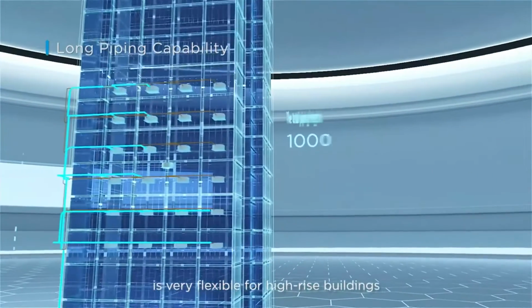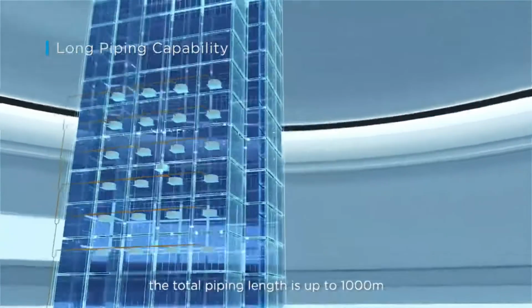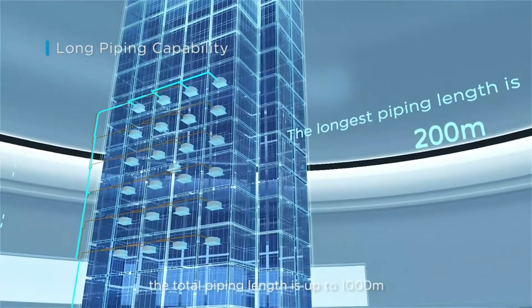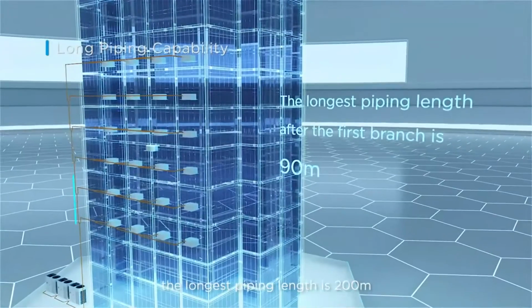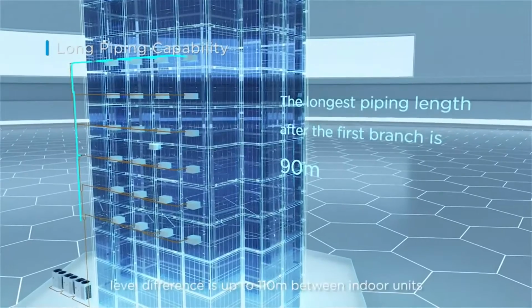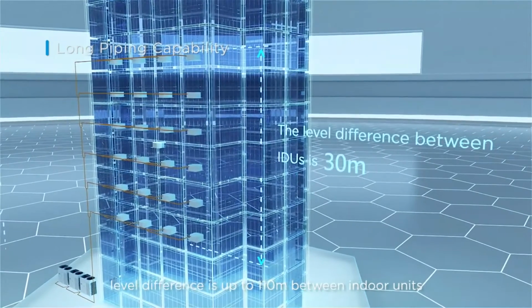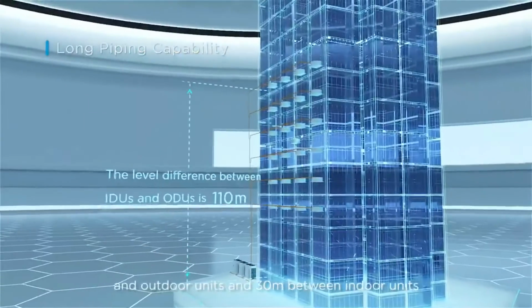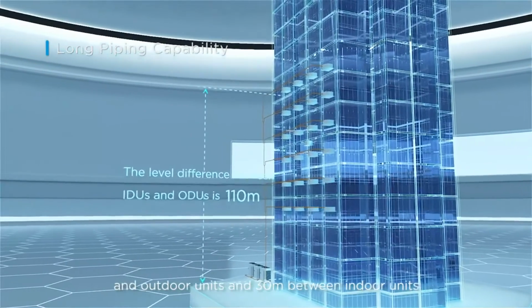VC Pro Series VRF is very flexible for high-rise buildings. The total piping length is up to 1,000 meters. The longest piping length is 200 meters. Level difference is up to 110 meters between indoor units and outdoor units, and 30 meters between indoor units.